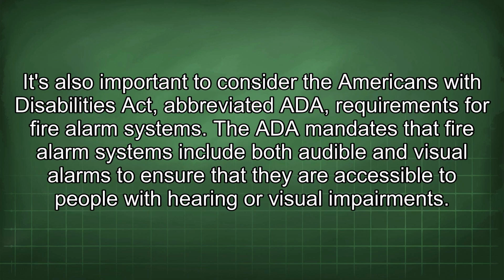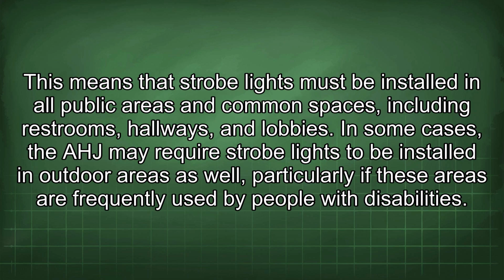It's also important to consider the Americans with Disabilities Act, abbreviated ADA, requirements for fire alarm systems. The ADA mandates that fire alarm systems include both audible and visual alarms to ensure that they are accessible to people with hearing or visual impairments. This means that strobe lights must be installed in all public areas and common spaces, including restrooms, hallways, and lobbies. In some cases, the AHJ may require strobe lights to be installed in outdoor areas as well, particularly if these areas are frequently used by people with disabilities.